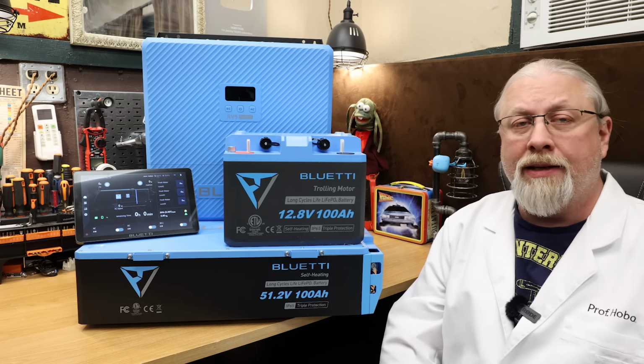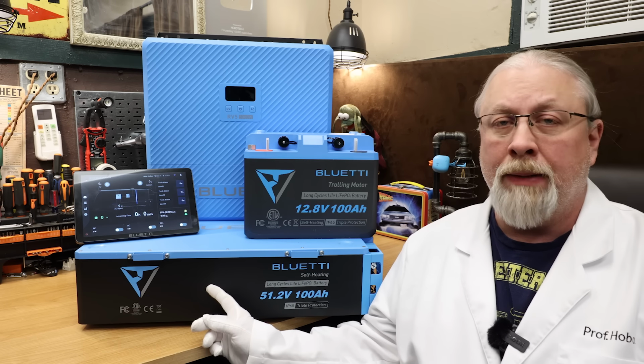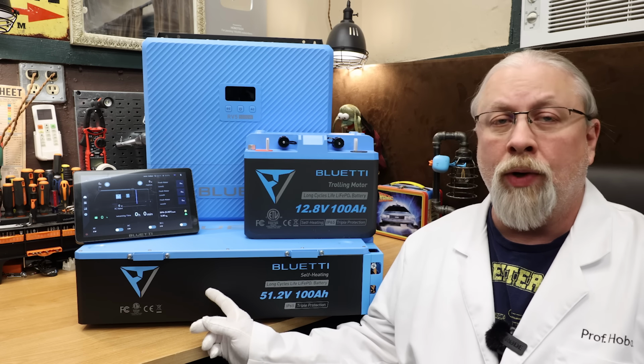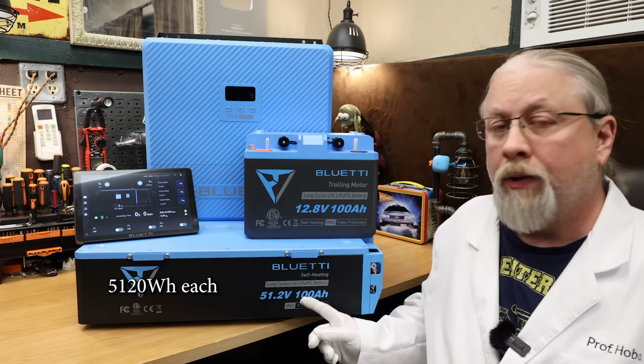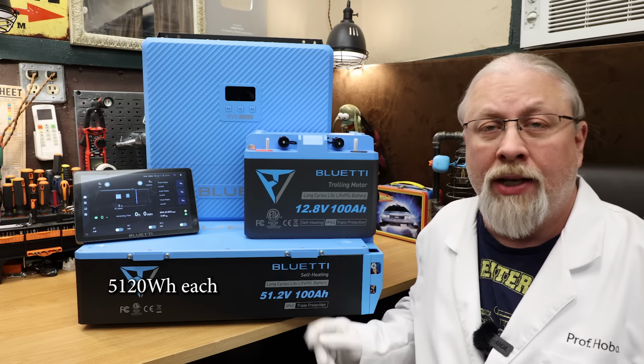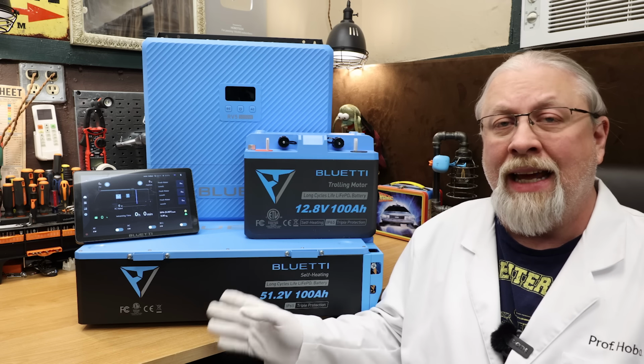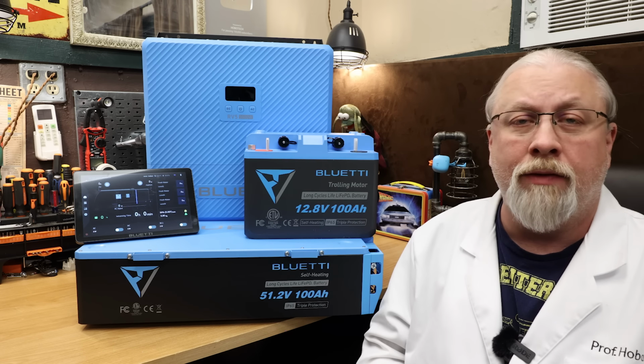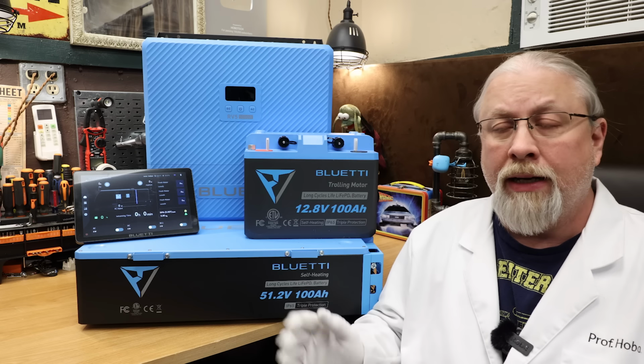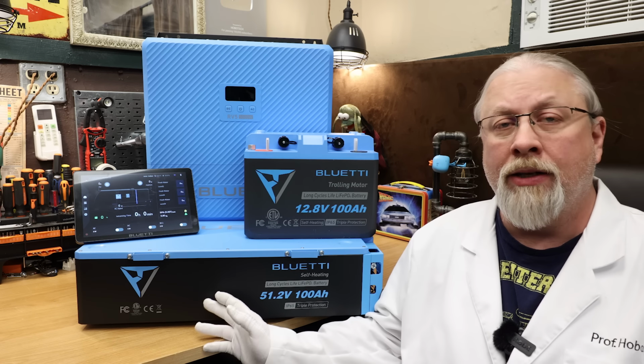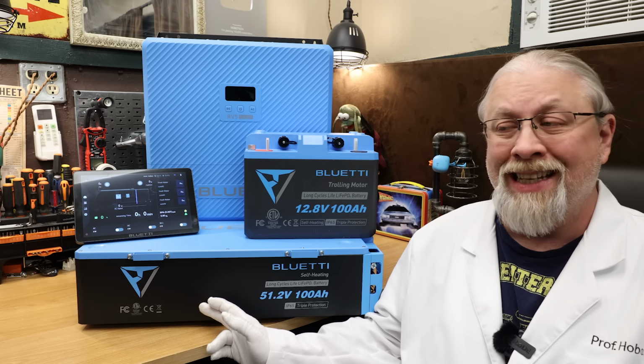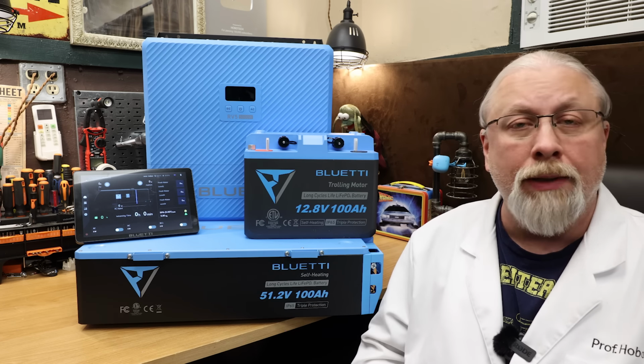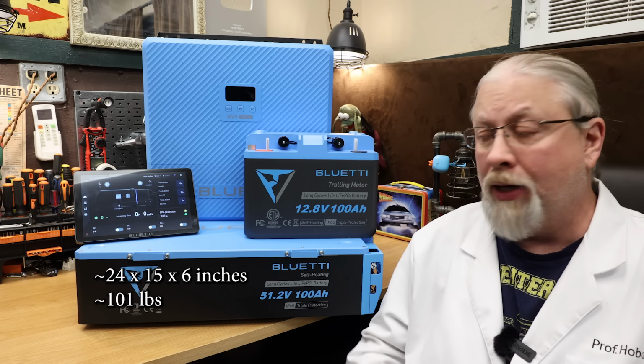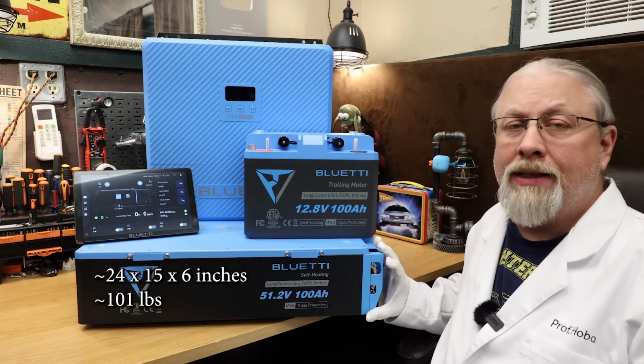Now on to the specs. The B4810 LFP batteries are 51.2 volt 100 amp hour for 5,120 watt hours each, and as previously mentioned are heated and IP65 water resistant for placing outdoors or in an uninsulated compartment. They have a 100 amp BMS on board and are rated for 6,000 cycles. They're approximately 101 pounds each and are about 24 by 15 by 6 inches.